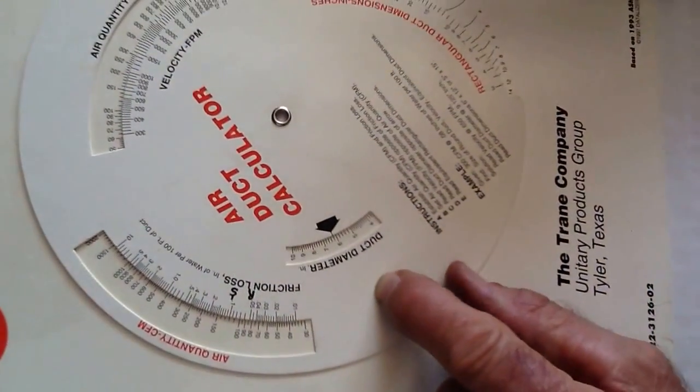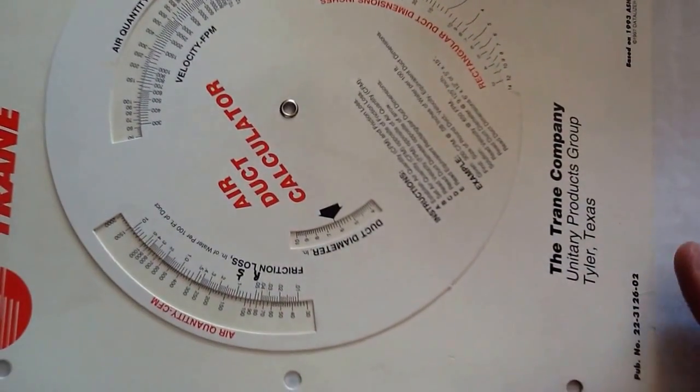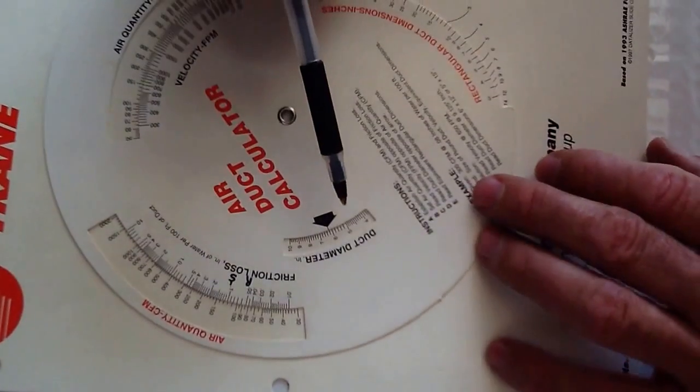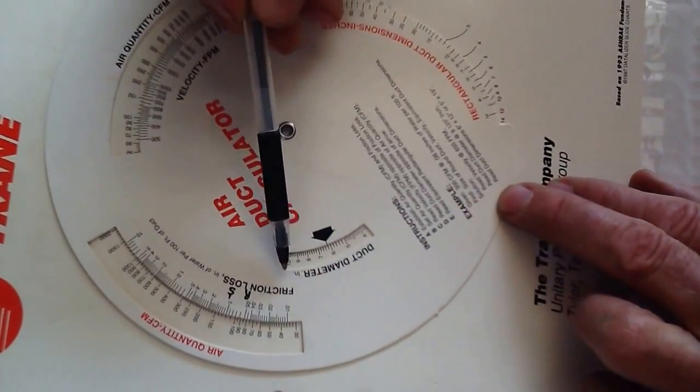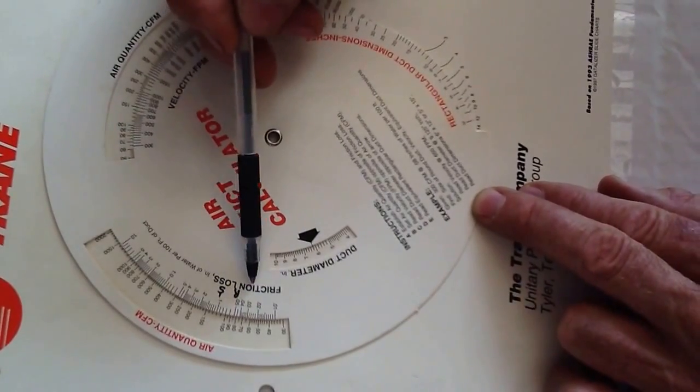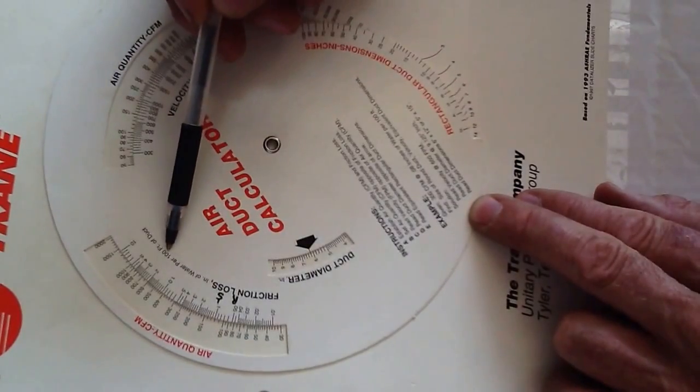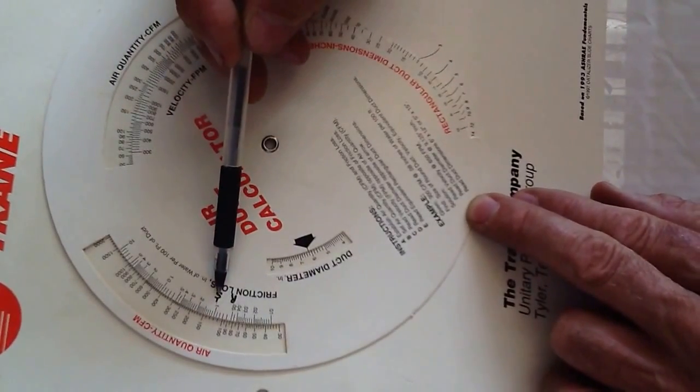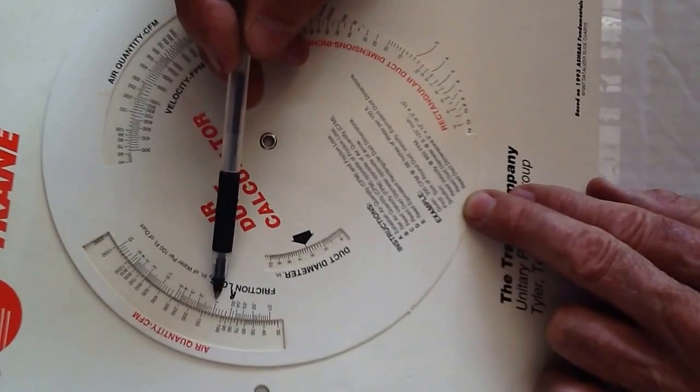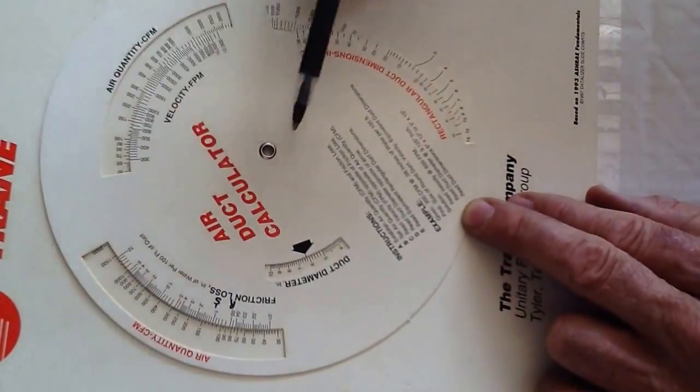Now let's talk about what we got here. We have duct diameter, you have supply - this is the friction loss chart per hundred feet of duct work. And you always do your supplies at 0.1 static pressure and return at 0.05.